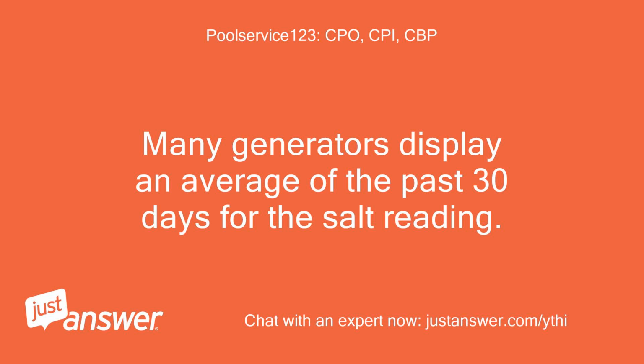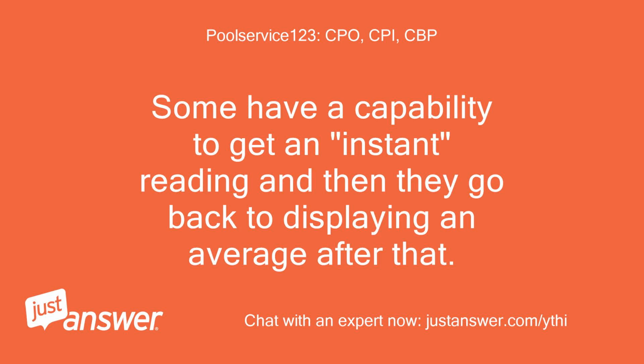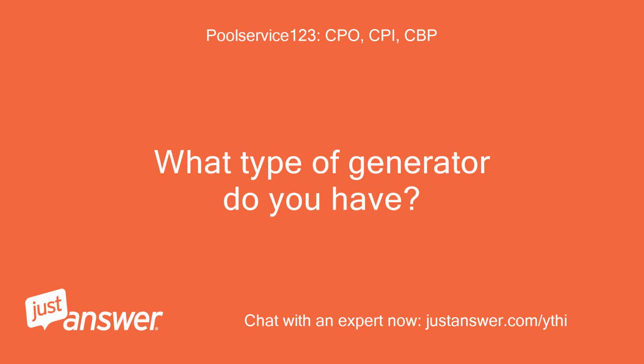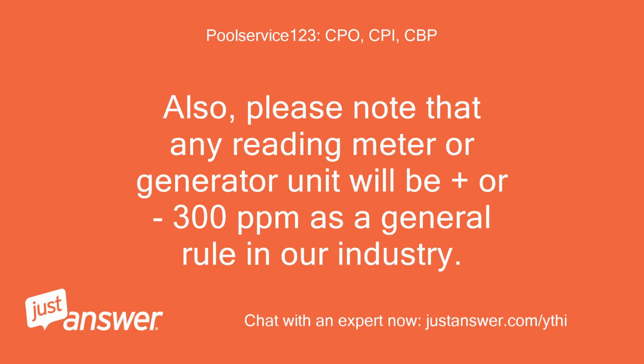Many generators display an average of the past 30 days for the salt reading. Some have a capability to get an instant reading and then they go back to displaying an average after that. What type of generator do you have? Also, please note that any reading meter or generator unit will be plus or minus 300 parts per million as a general rule in our industry.